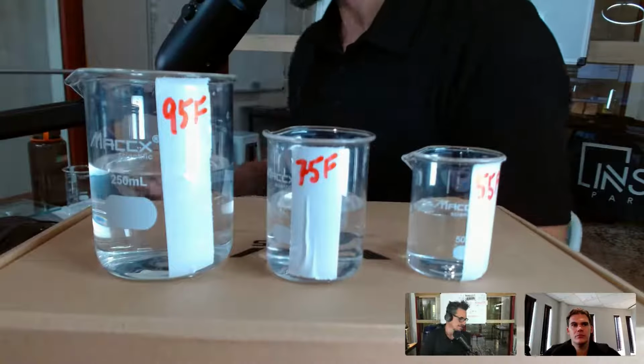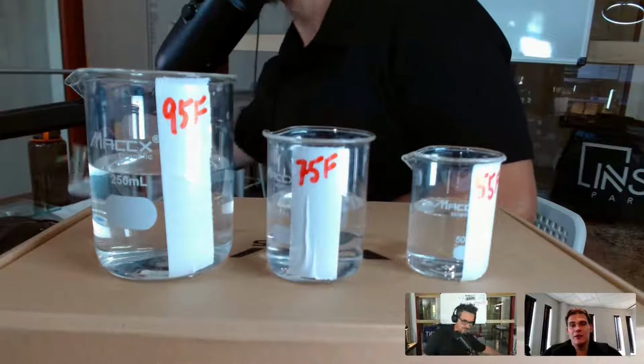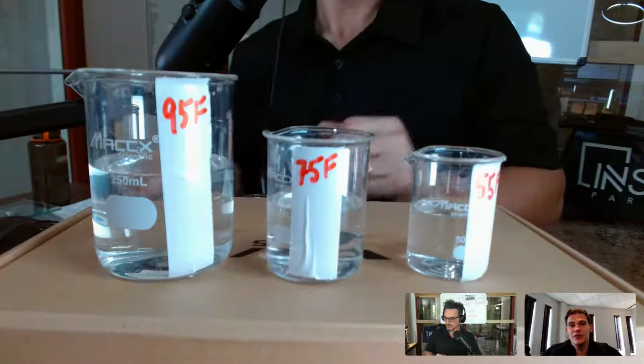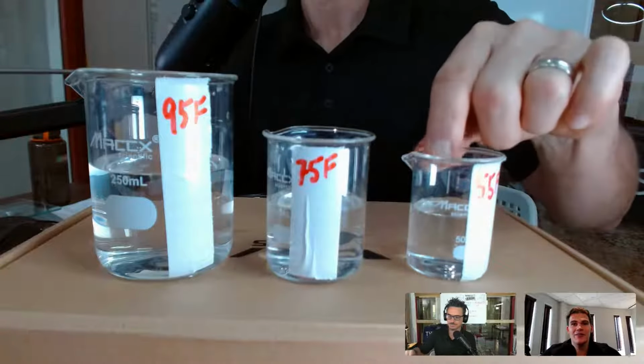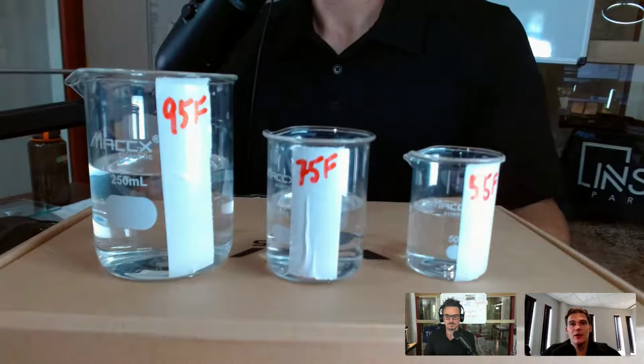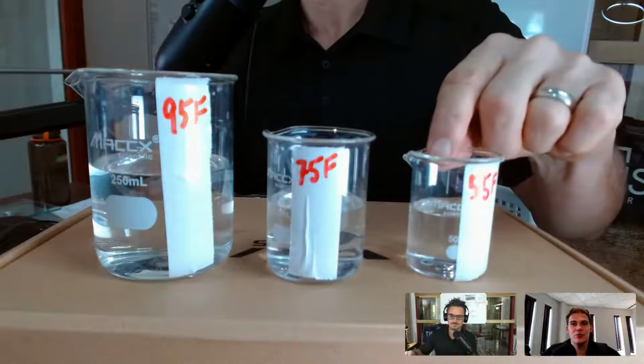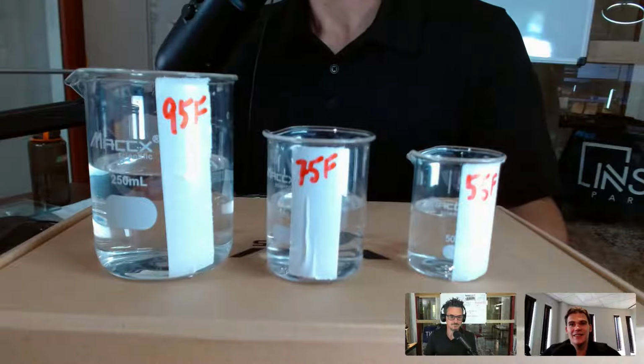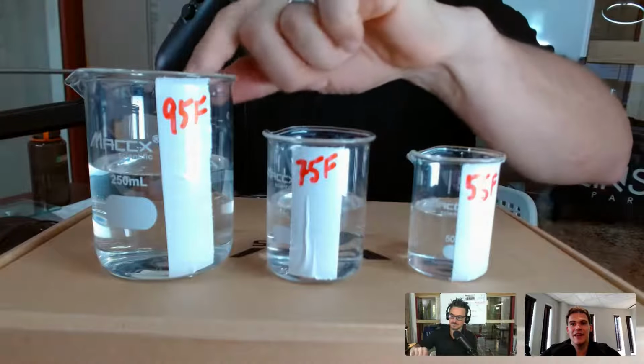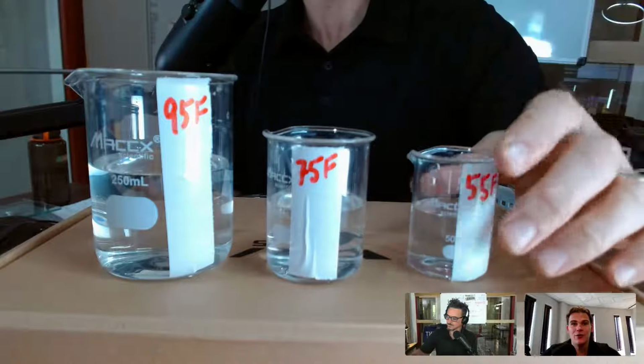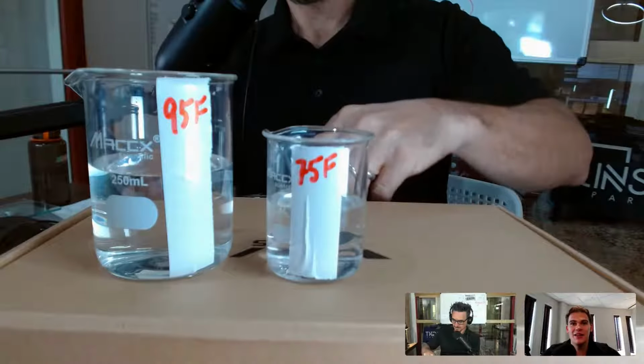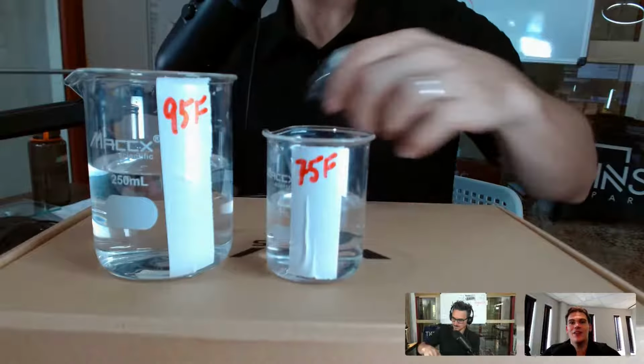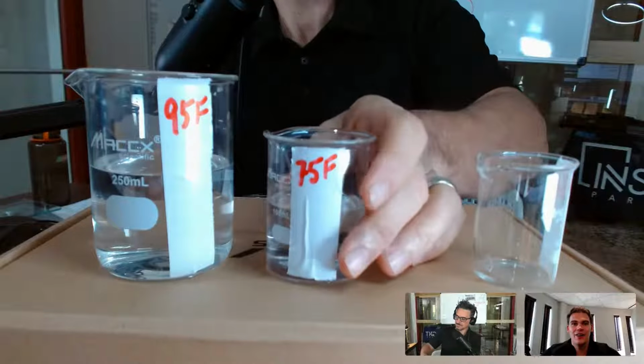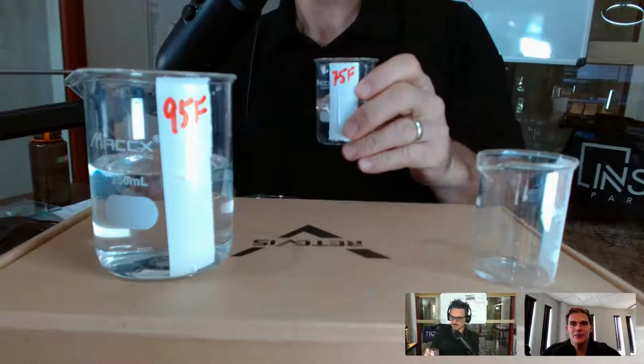Make sense, Kevin? Anything to add? Absolutely. One of the things I will run into sometimes is when people are not satisfied with the relative humidity in a space, they tend to try to turn down the temperature. I think this gives a really good example. If all we cared about was decreasing relative humidity, and we took that 55-degree beaker and poured it into the 75, our relative humidity is going to be lower. Yep.